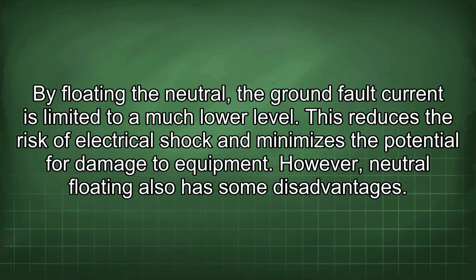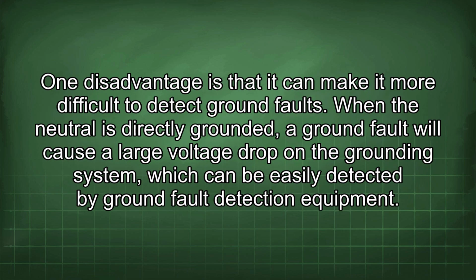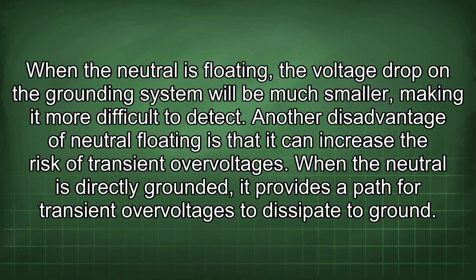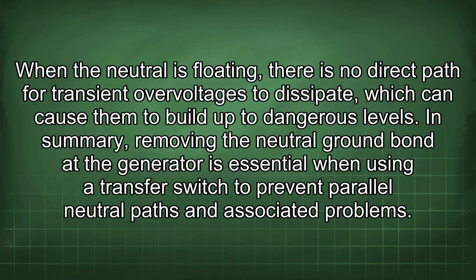However, neutral floating also has some disadvantages. One disadvantage is that it can make it more difficult to detect ground faults. When the neutral is directly grounded, a ground fault will cause a large voltage drop in the grounding system, which can be easily detected by ground fault detection equipment. When the neutral is floating, the voltage drop in the grounding system will be much smaller, making it more difficult to detect. Another disadvantage of neutral floating is that it can increase the risk of transient overvoltages. When the neutral is directly grounded, it provides a path for transient overvoltages to dissipate to ground. When the neutral is floating, there is no direct path for transient overvoltages to dissipate, which can cause them to build up to dangerous levels.